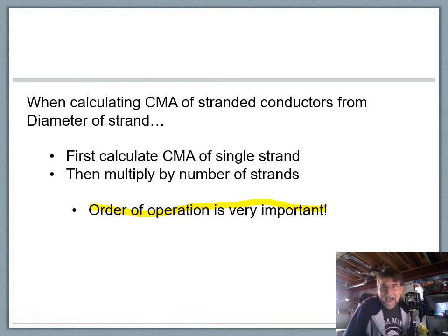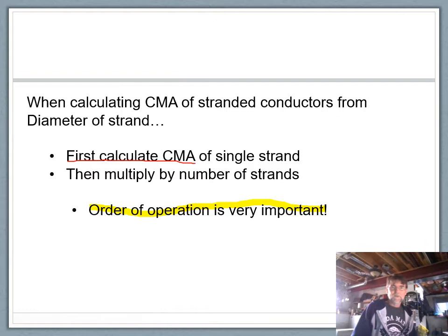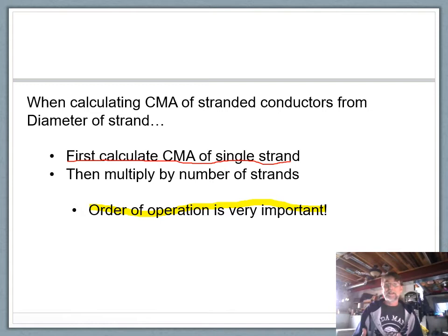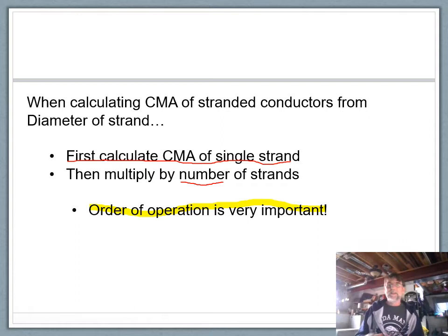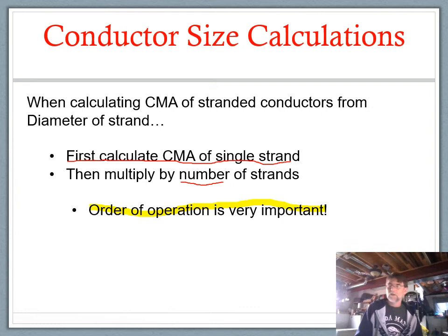If you're given a question that tells you the diameter of a strand and your task is to find the circular mil area of the entire conductor, step one must be: first calculate the circular mil area of a single strand. Square the strand diameter to get the circular mil area of that strand, then multiply by the number of strands. That gives you the circular mil area of the entire conductor. It's really important to do it in that order.